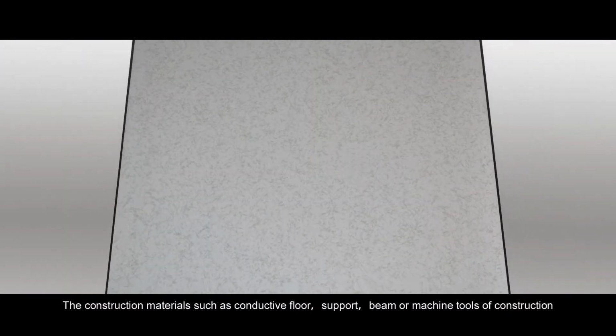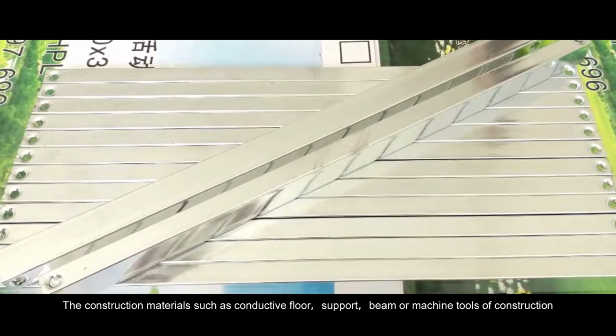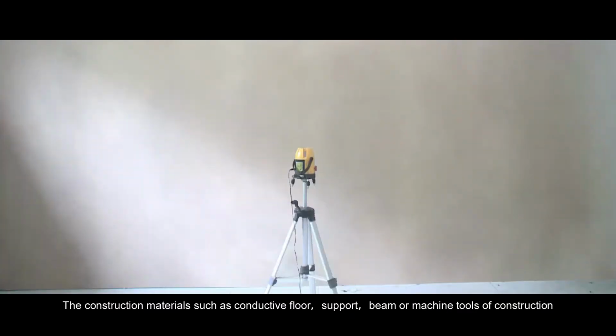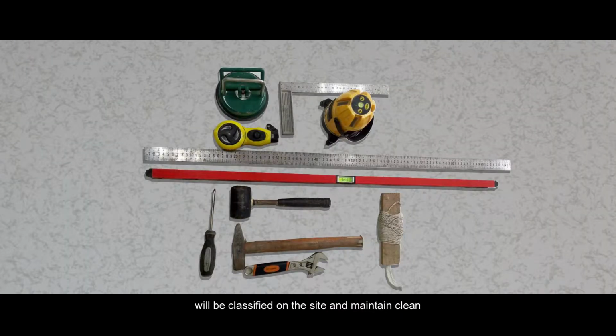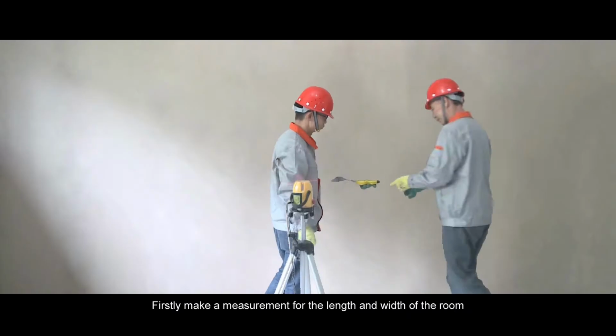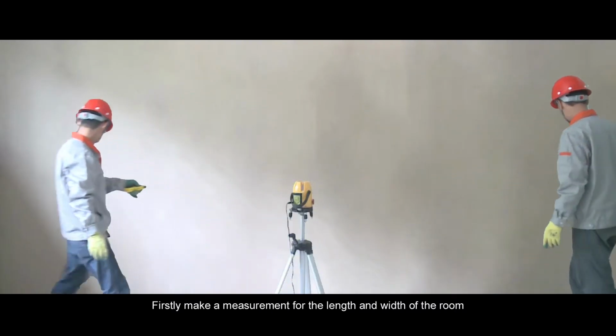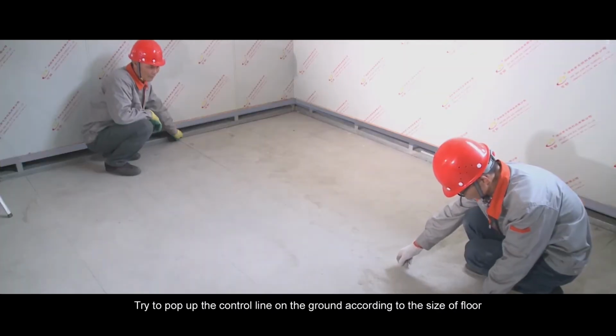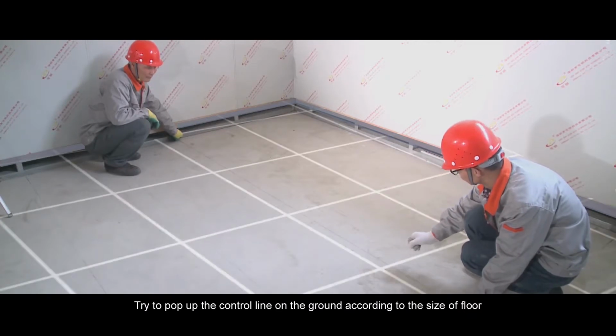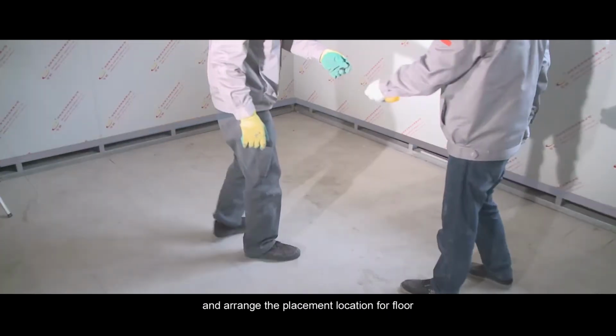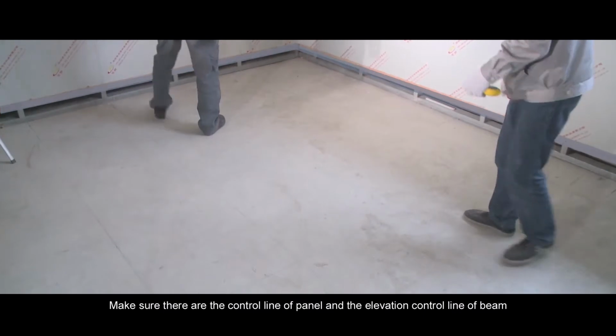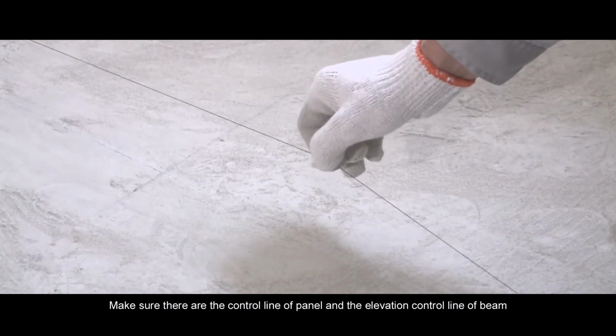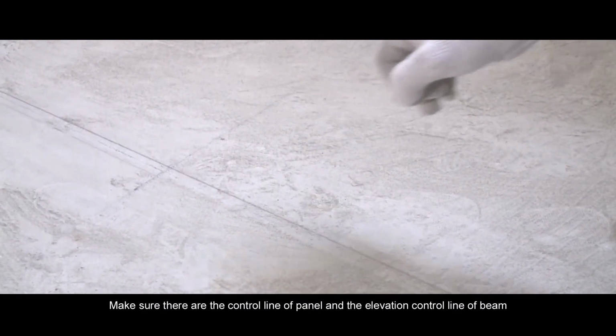The construction materials such as conductive floor, support, beam, or machine tools of construction will be classified on the site and maintained clean. Firstly, make a measurement for the length and width of the room. Try to pop up the control line on the ground according to the size of floor and arrange the placement location for floor. Make sure there are the control line of panel and the elevation control line of beam.